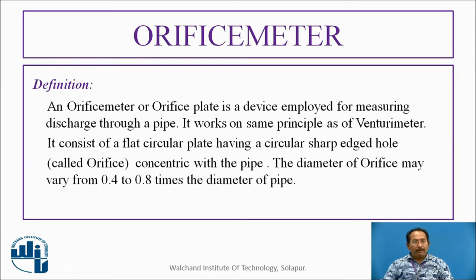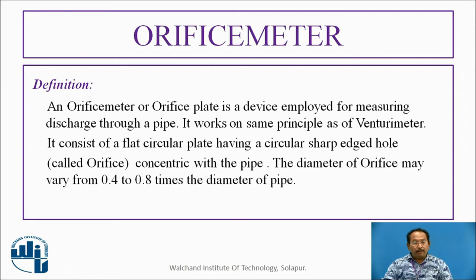An orifice meter, or orifice plate, is a device employed for measuring the discharge. It works on the same principle as the Venturimeter. It consists of a flat circular plate having a circular sharp-edged hole. The diameter of the hole is called the orifice, which is concentric with the pipe. The diameter of the orifice may vary from 0.4 to 0.8 times the diameter of the pipe.